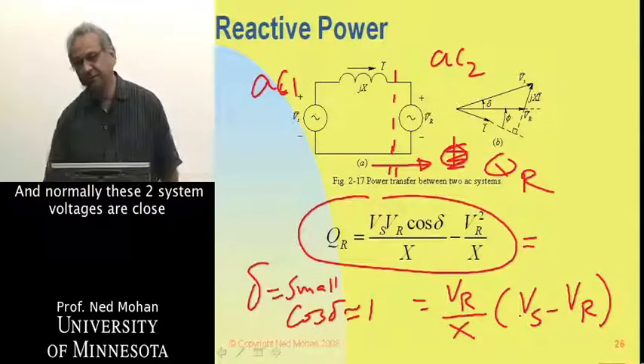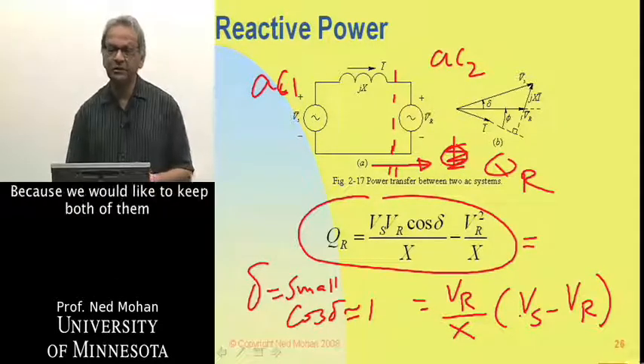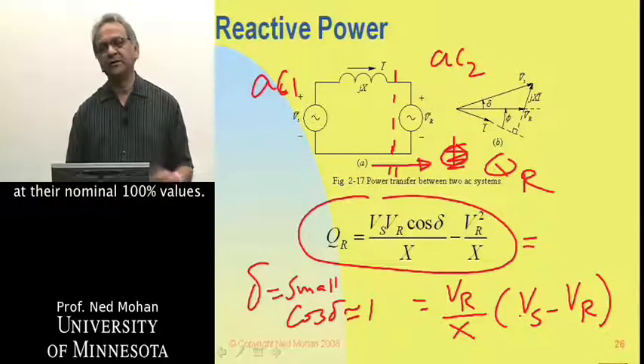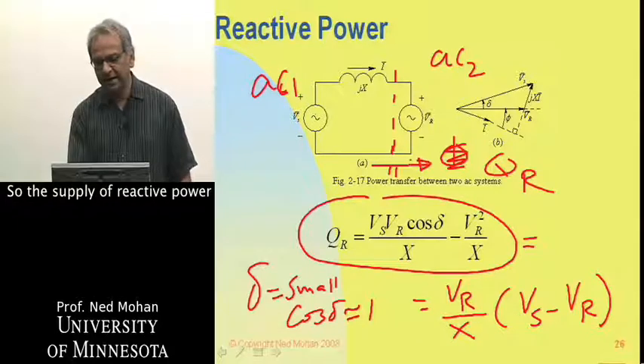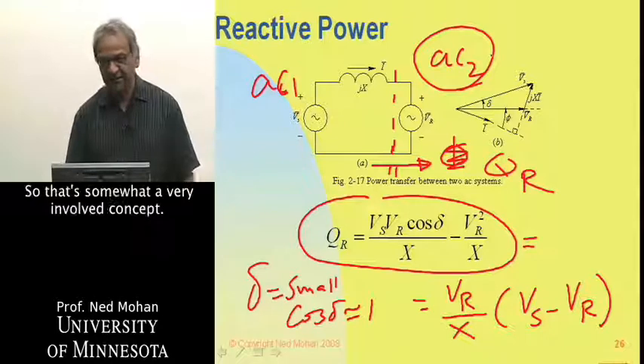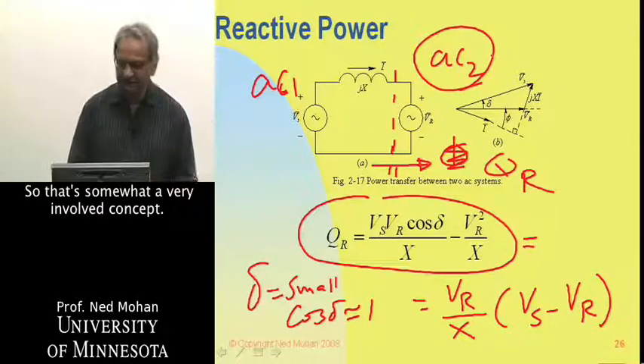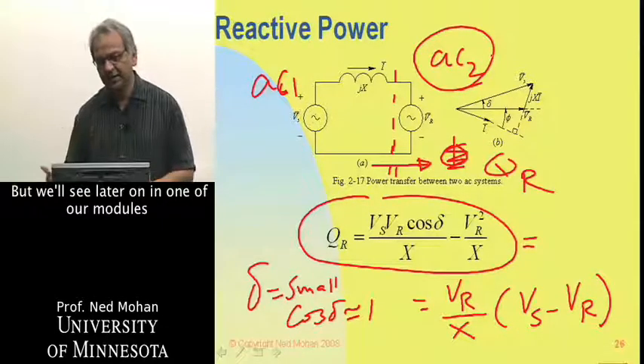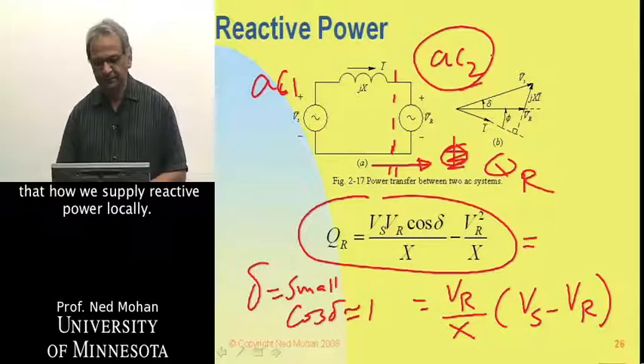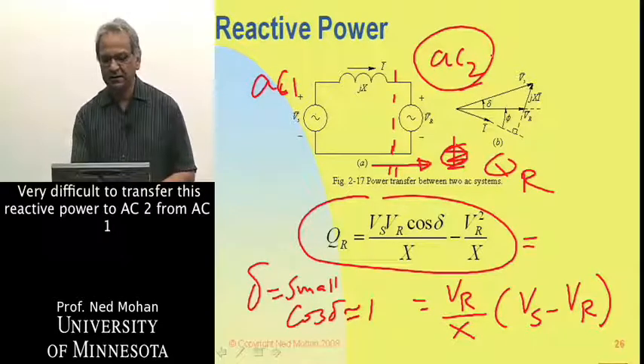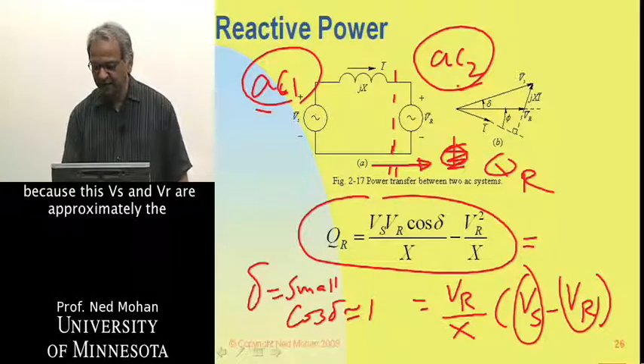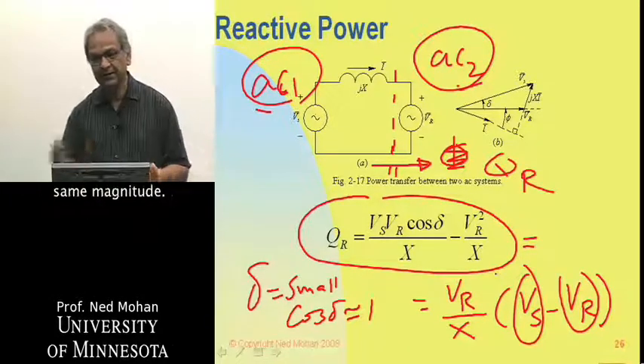Normally these two system voltages are very close to each other, because we want to keep both at their nominal 100% values. So the supply of reactive power to AC system 2 really becomes a local affair. It's very difficult to transfer reactive power from AC system 1 to AC system 2 because Vs and Vr are approximately the same magnitude.